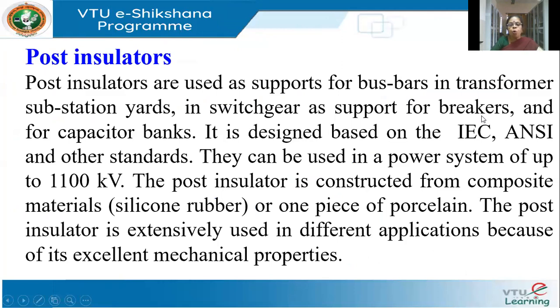We have something called as post insulators. They are normally used as supports for bus bars in transformers, in substation yards, and also in switch gears to support the circuit breakers and for capacitor banks. Capacitor banks are normally connected for improvement of power factor and also as voltage profile builders — they will improve the voltage profiles.